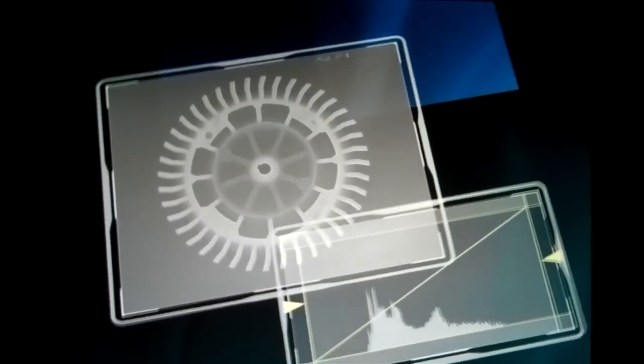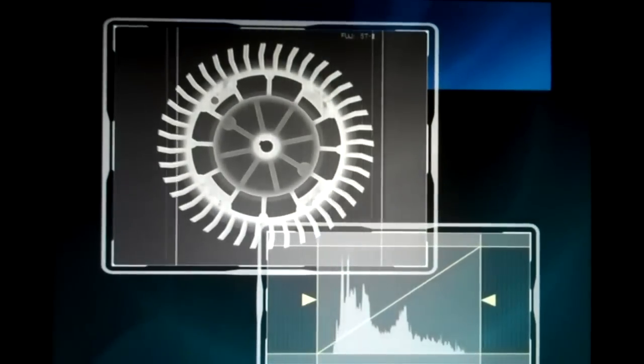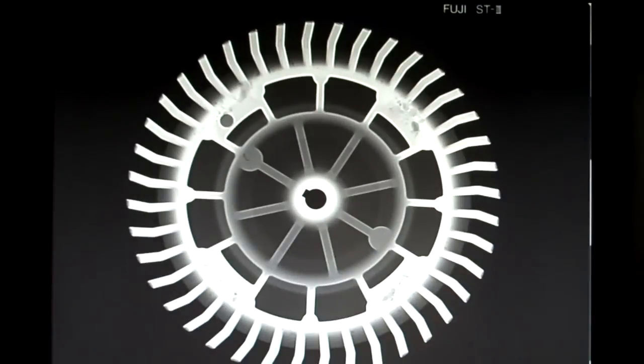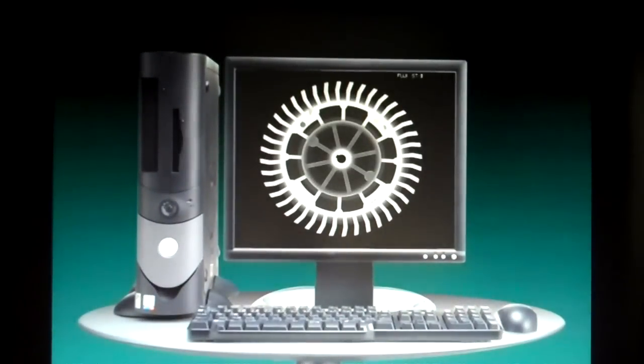Here we will demonstrate the EDR function. The characteristics of the imaging plate are that the range of the X-ray absorption area is wide, and at the same time, the ratio between the X-ray absorption and the photostimulated emission shows a complete diagonal linearity. The EDR function instantaneously makes a histogram analysis of the scanned image data and extracts only the area needed for output and secures the density data. The EDR then creates an optimized image from the density data after making the necessary adjustments.